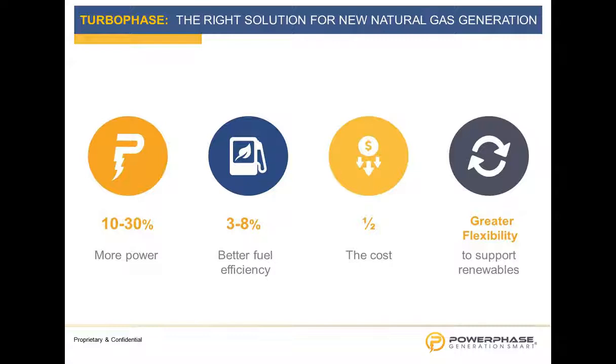Unlike a turbine upgrade or something that's specific to your gas turbine, this is a power plant solution. When we install Turbophase into the power station, we connect it to all the gas turbines in the power station. We can direct that air to any gas turbine that is operational. So we have clients where they may have 4 gas turbines, 3 of which run. One's in a hot standby, and they rotate every week, which 3 run. This allows them not to have to upgrade all 4 turbines, but upgrade just the power station with Turbophase and direct the air where they'd like. It also allows them to offset planned shutdowns.